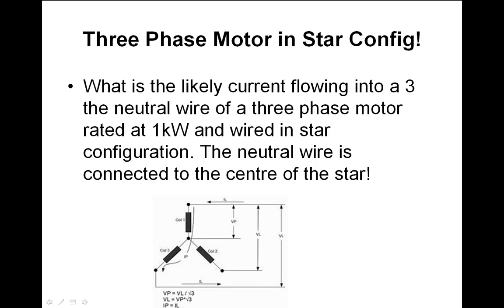Three-phase motor configurations — star and delta. Question: what is the likely current flowing into the neutral wire of a three-phase motor rated at 1 kilowatt and wired in star configuration, with the neutral wire connected to the center of the star? The answer is zero. The rule is: in a balanced system, the neutral should carry zero current.